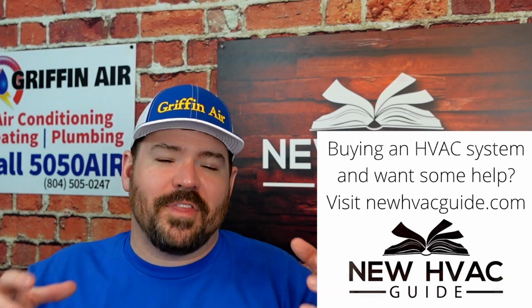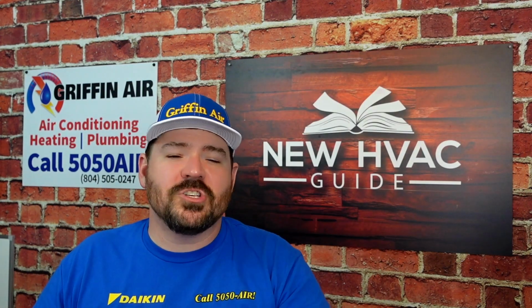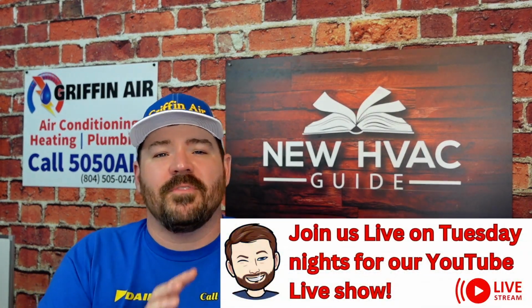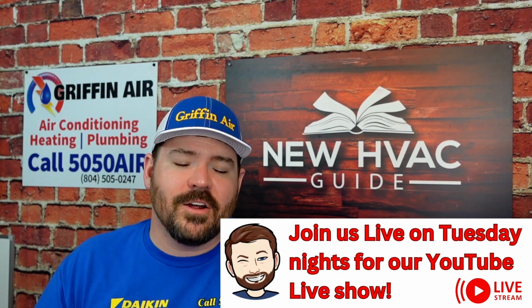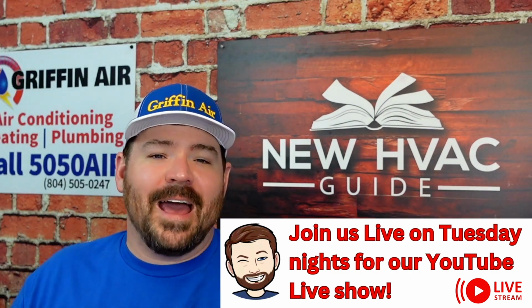Any problems with that fan wheel, the housing, anything that's holding all of that together, any of that can cause vibrations. We've had tons of customers in the past that have vibrating issues. Replacing the motor and the fan wheel takes care of it, never hear from them again in a good way, and that is their fix.